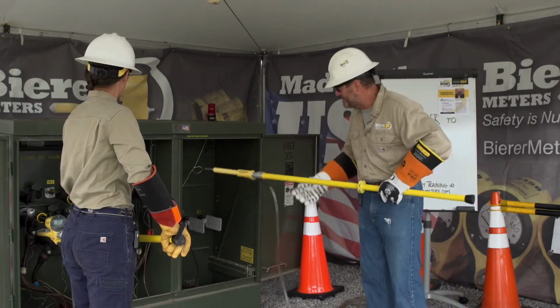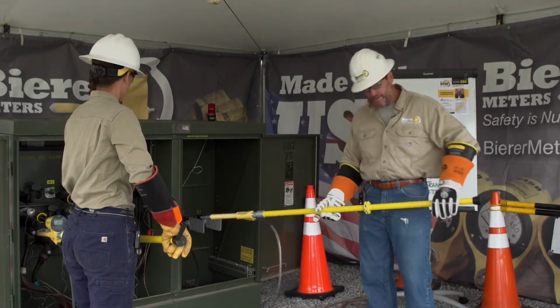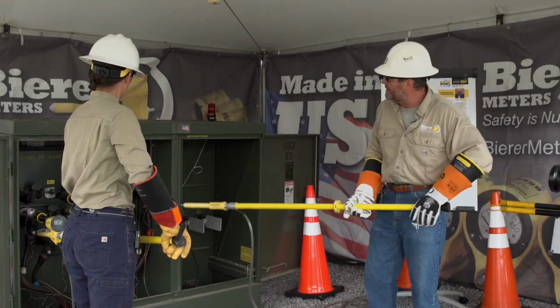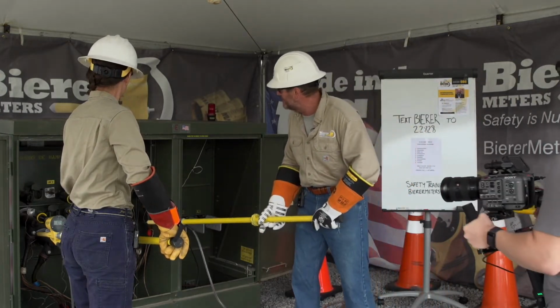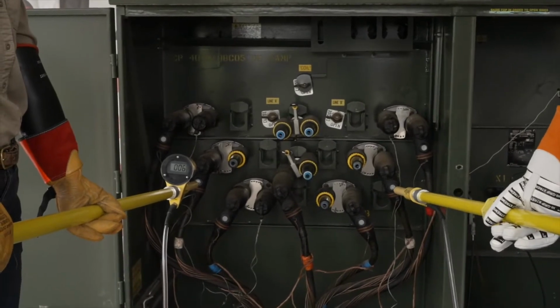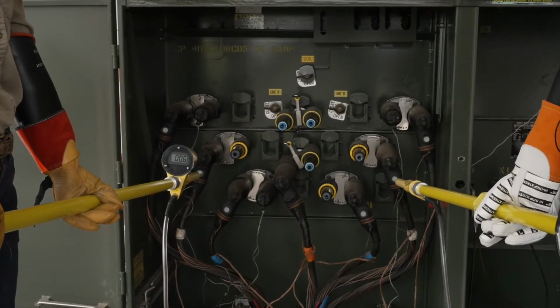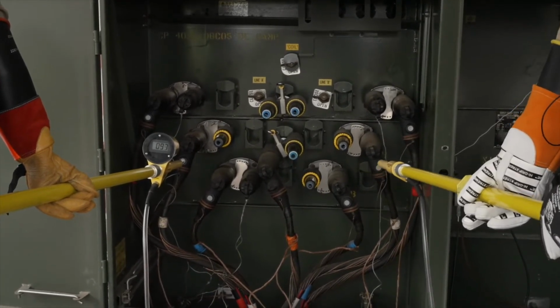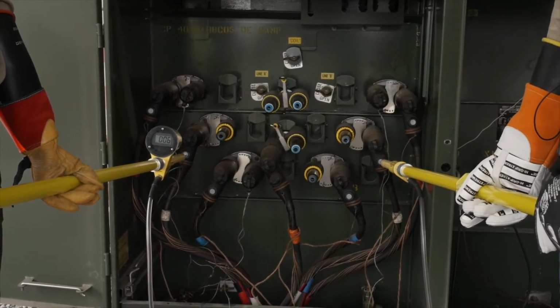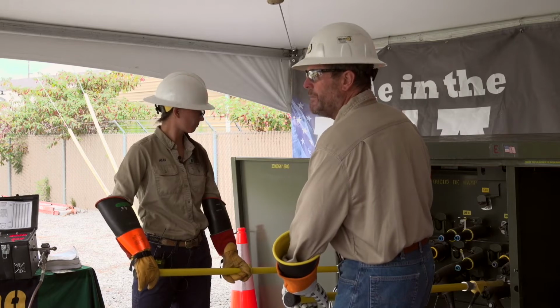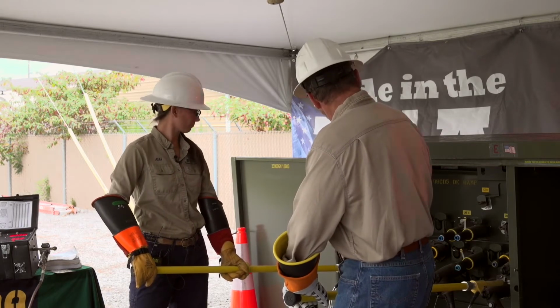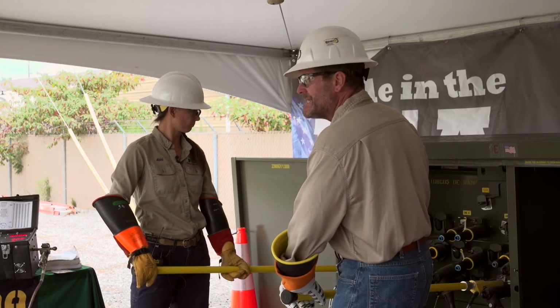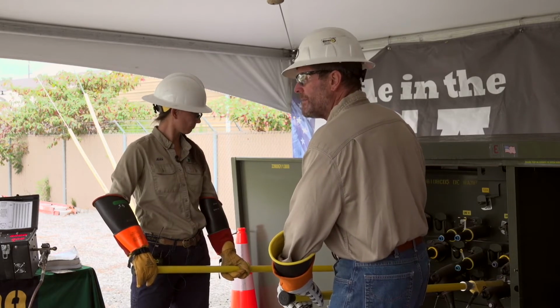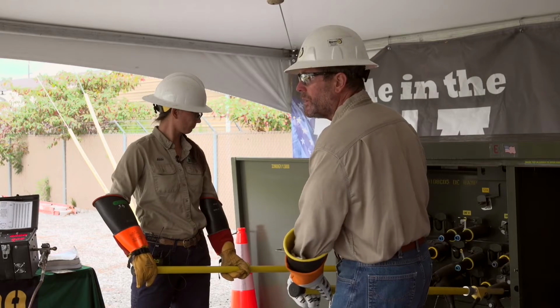And so I'm going to go ahead to this other side of the cabinet, or that other overhead conductor, and we're going to verify if we're in phase or out of phase. What you got, Abby? 6 volts. All right, so we're really close to 0. We know that these elbows, because they're a little different, have a little bit of difference of semicon material, a fingerprint you might say, they're not exactly the same. So they're going to have a little bit of difference of resistance. Therefore, you're not going to get 0 necessarily, but we're real close, so we know we're in phase.